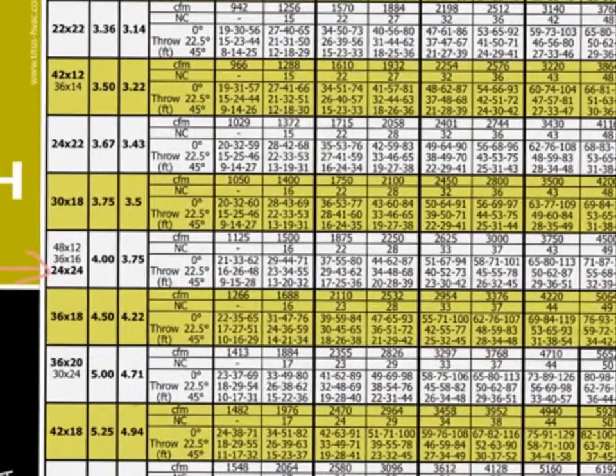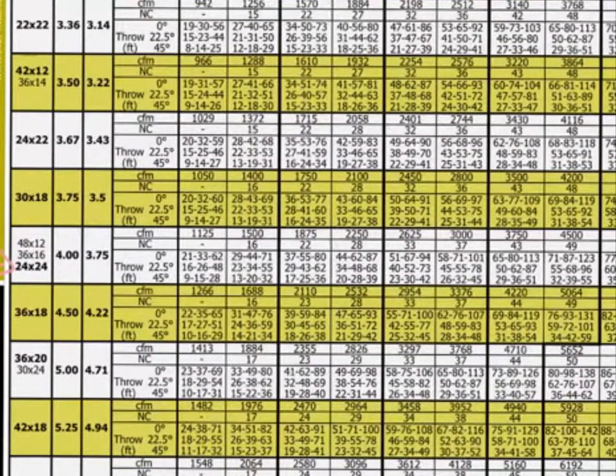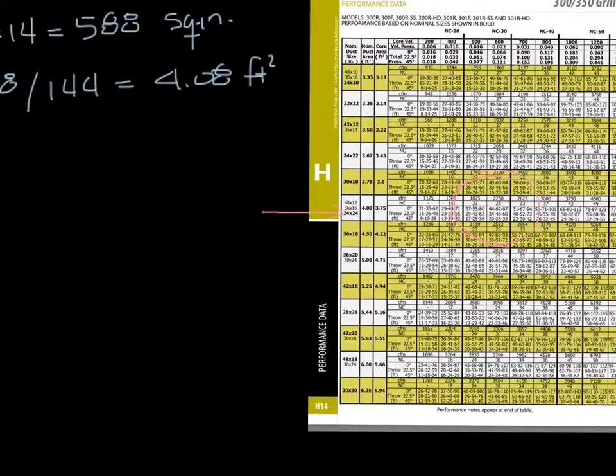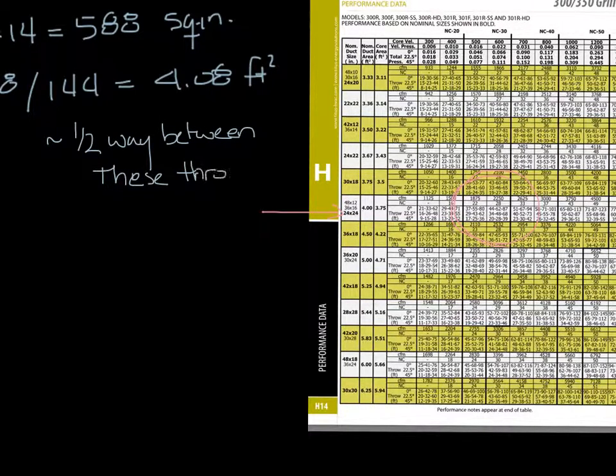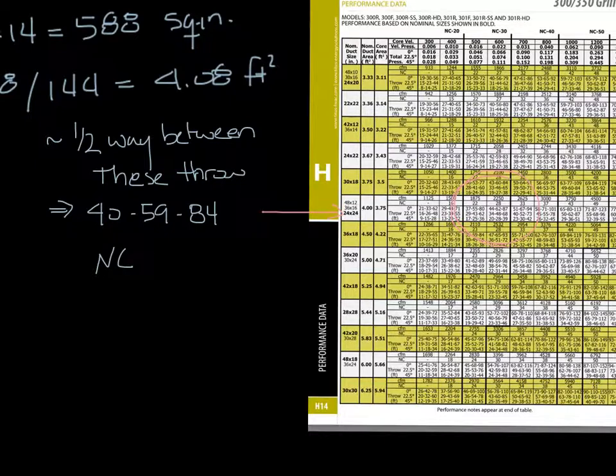Now find the airflow closest to 2000 CFM. In this case it's about halfway between 1875 and 2250 CFM, so the throw would be about halfway between those two throws — that's 40 at 150 feet per minute, 59 at 100, and 84 at 50 feet per minute. The sound would also be about halfway between NC-22 and NC-28, so about NC-25.